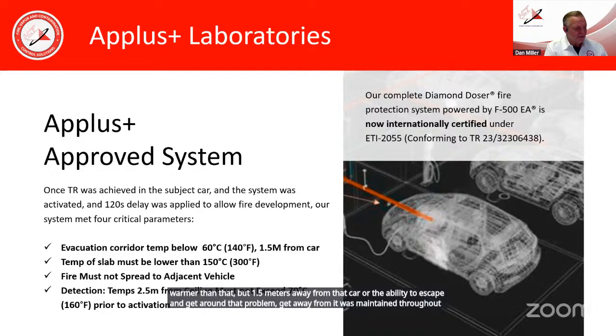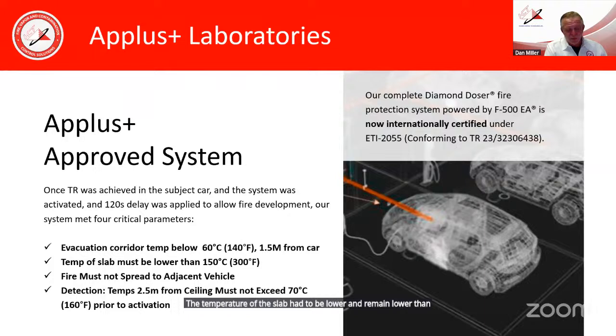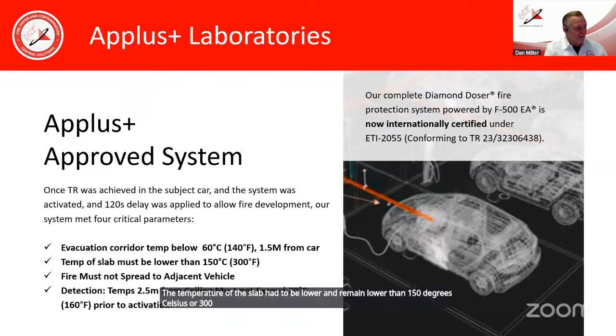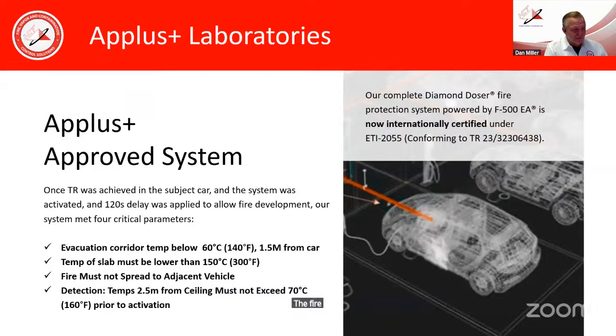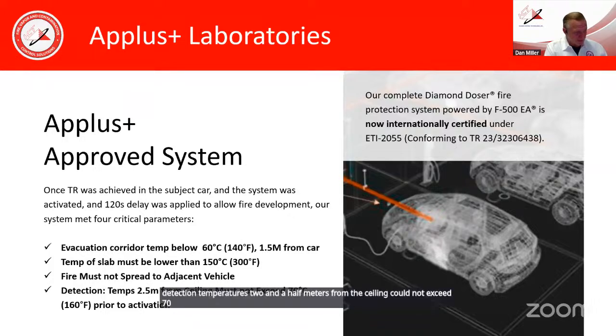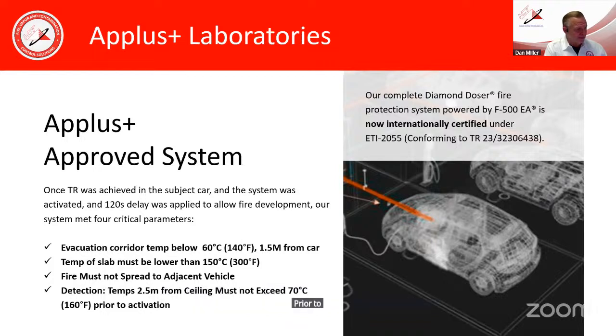The temperature of the slab had to be lower and remain lower than 150 degrees Celsius or 300 degrees Fahrenheit. The fire could not spread to the adjacent vehicle, and it did not. And the detection temperatures, 2.5 meters from the ceiling, could not exceed 70 degrees Celsius or 160 degrees Fahrenheit prior to activation, and they did not.